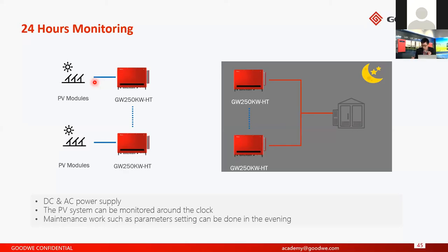At night, you can use AC power to power up the HT series, but the inverter will not generate. So the inverter is only powered up, and you can make some parameter settings, do the configuration, and do the firmware update.